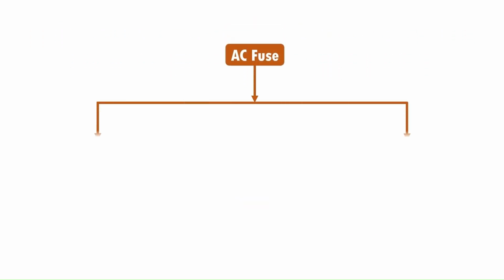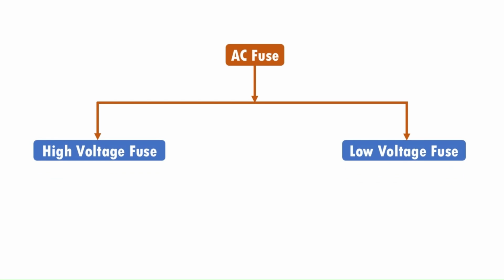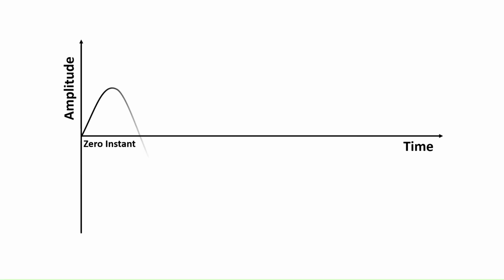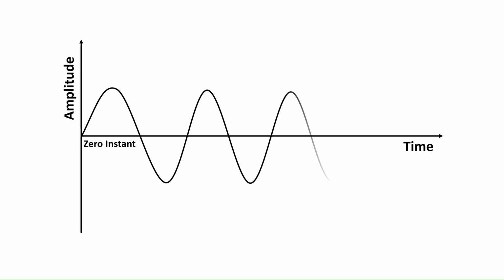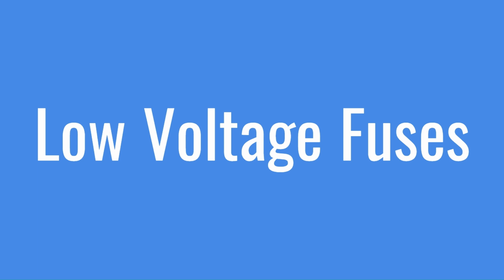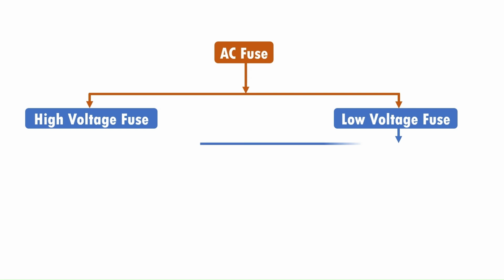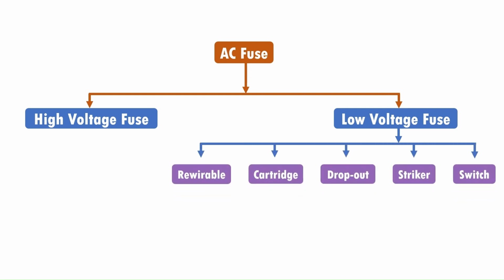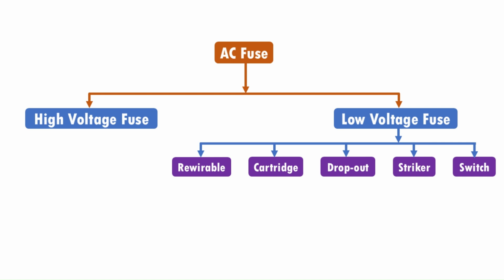The AC fuses are categorized into two types. They are the low voltage fuses and high voltage fuses. The alternating current changes its amplitude continuously. The current touches the zero instant 100 times in 1 second in a 50 Hz cycle. Thus, the arc extinction in the AC circuit can be done easily as compared to the DC circuit. The low voltage fuses are further divided into rewirable fuse, cartridge fuse, dropout fuse, striker fuse, and switch fuse.